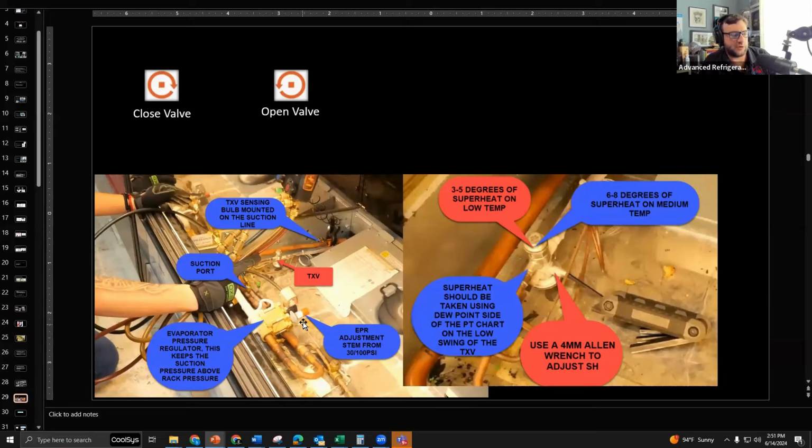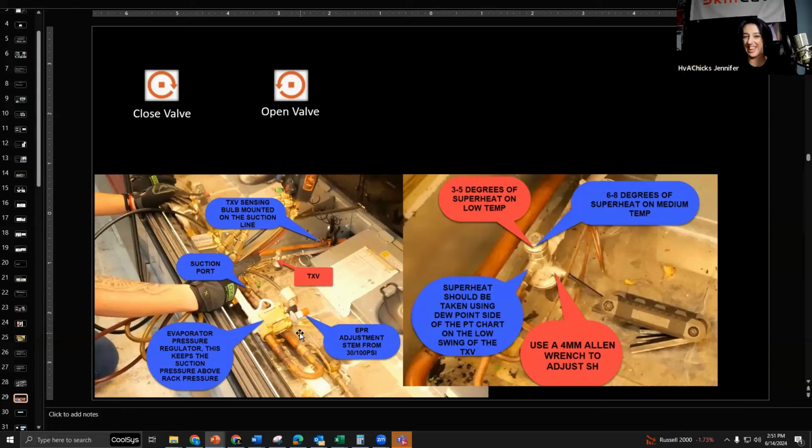Essentially, if you really think about it, we only have three different types of valves that we deal with. I know there's hundreds of models and model numbers all over the place, but really there's only three different types of valves. And you're going to be like, no, you're full of it. No, listen, there's only three different kinds of regulating valves. You have an inlet pressure regulator, outlet pressure regulator, and differential. That's it. If you go that way with it, yes. It doesn't matter the model number. It's still doing one of those three things.